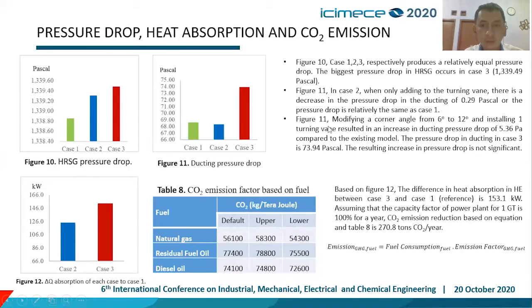Figure 11, modifying the corner angle from 6 to 12 degrees and installing one turning fin in case 3 resulted in an increase in ducting pressure drop of 5.36 Pascal compared to the existing model, case 1. Pressure drop in ducting in case 3 is 73.94 Pascal. The resulting increase in pressure drop is not significant.